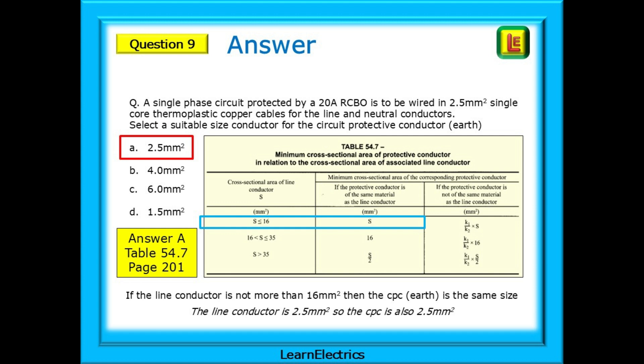Here, the line conductor is 2.5 square millimetre, so the CPC is also 2.5 square millimetres. How to find table 54.7 from the index is fairly straightforward. The question uses the word select. Turn to page 600 of the index. This is protective conductors, and just a few lines down on the left-hand side are the words selection and erection, section 543, from where table 54.7 is found on page 201.